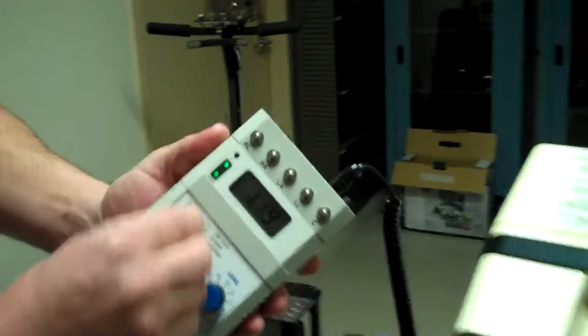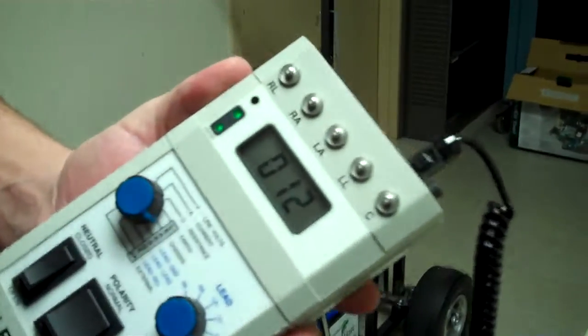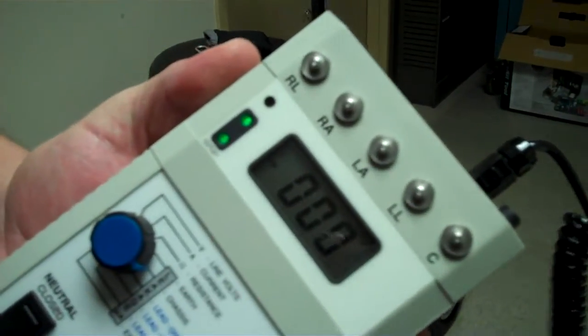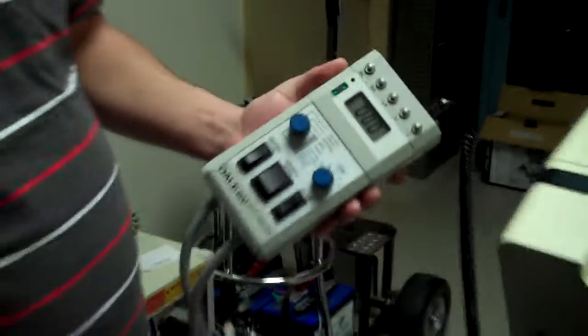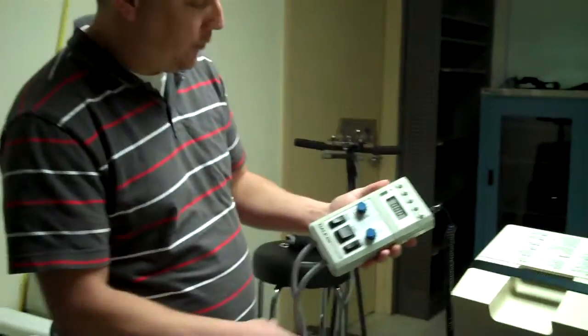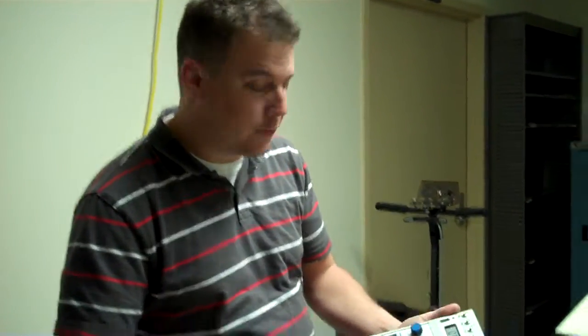So we're going to switch the knob over here to chassis, and you can see that it's reading 0, and that's exactly what we want. So as far as the electrical safety, everything's great. So we're going to move on over to the defibrillator analyzer, and we're going to check the discharge, the joules of the discharge for the defibrillator, and make sure that they are correct.